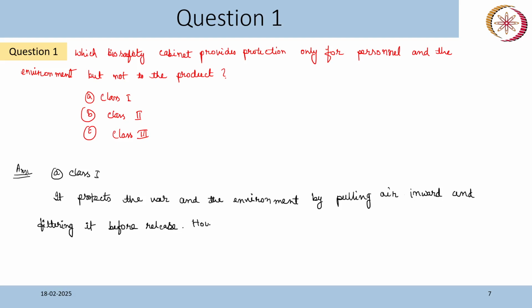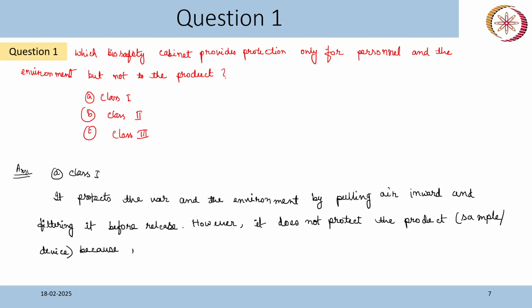However, it does not protect the product, that is your sample or device, because unfiltered air goes inside.